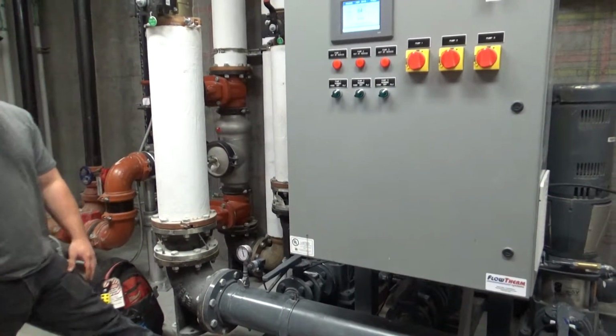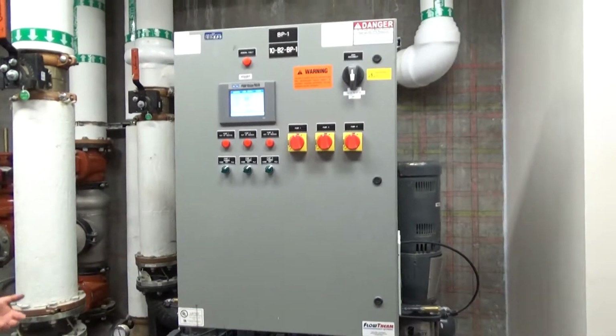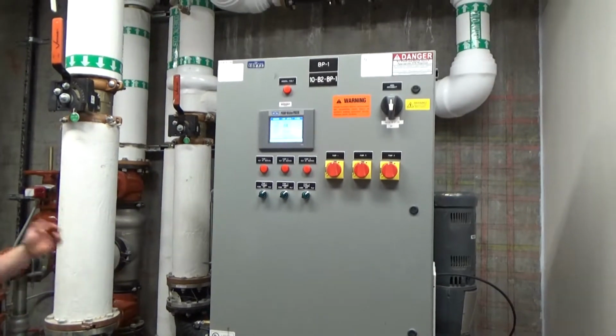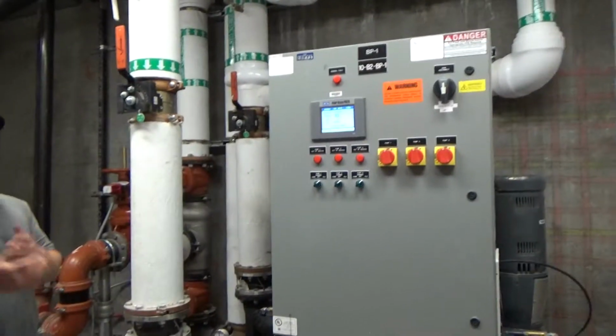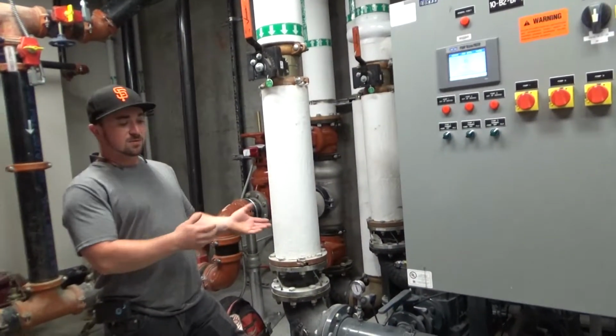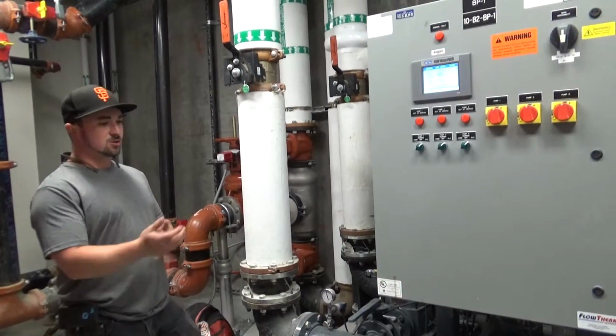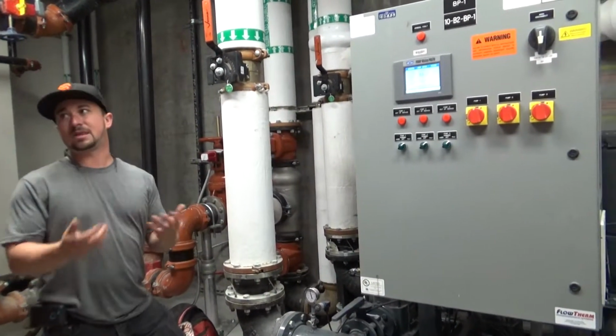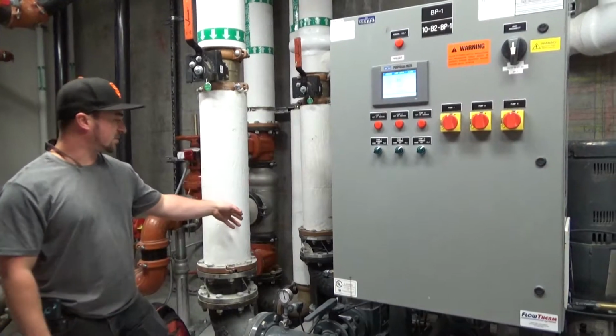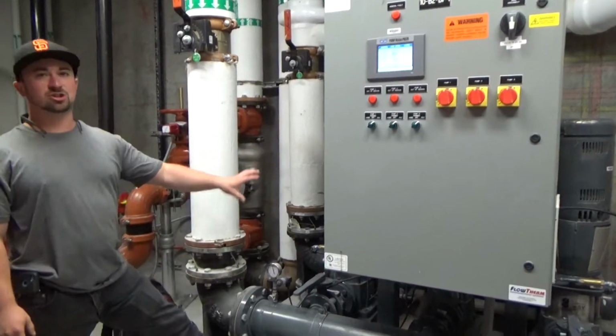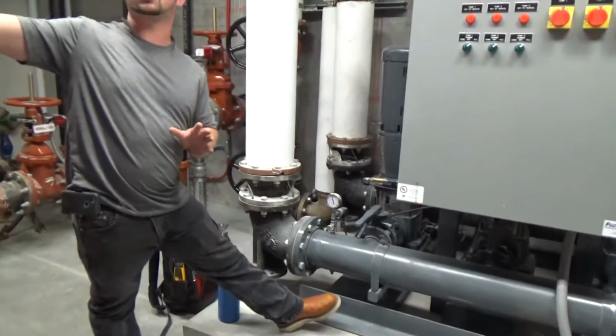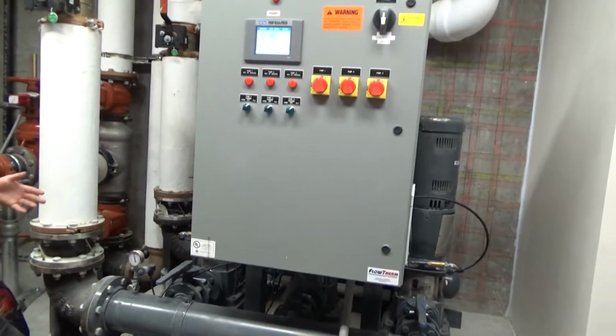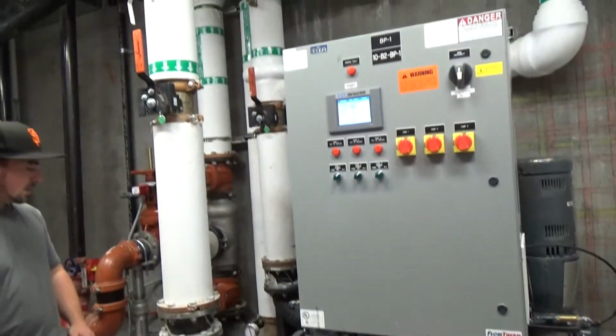What's nice about these panels is they have all sorts of alarms and safeties and stuff to make sure that if something happens, it will shut itself down or do whatever the alarm calls for. It knows there's certain things that happen when that alarm happens. So if it's a high suction alarm, it'll make sure to turn off the pump so you don't overpressurize anything else further down the line. So certain alarms do certain things.